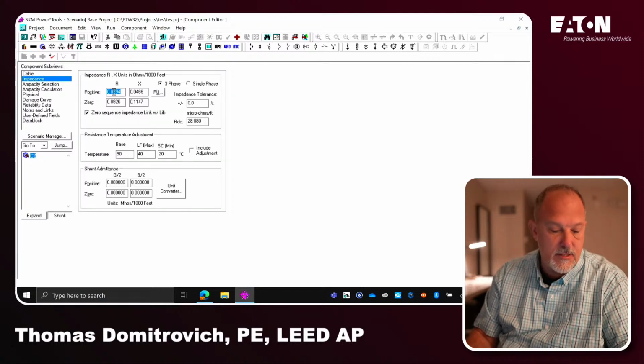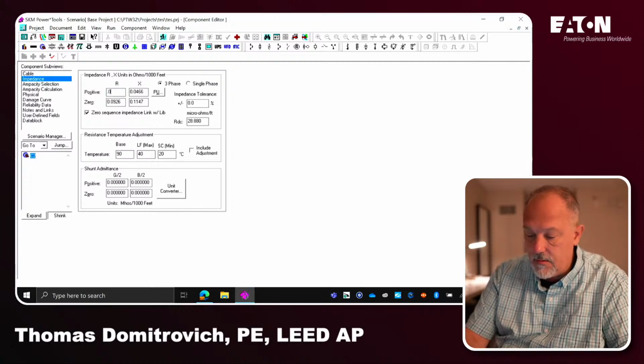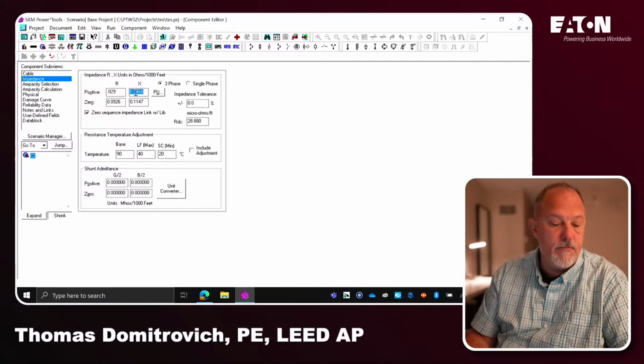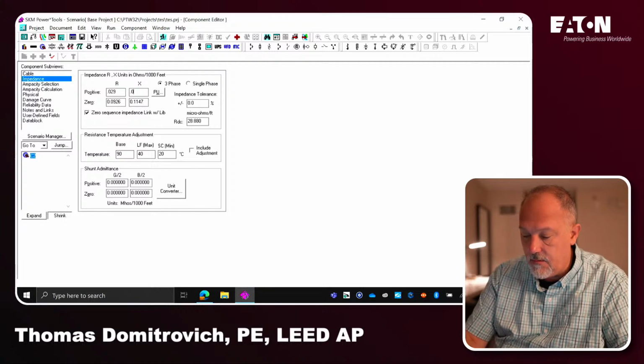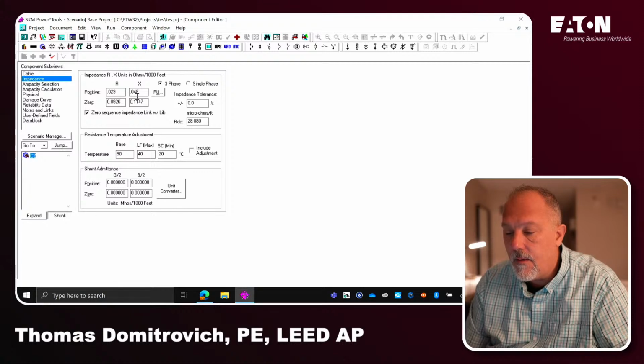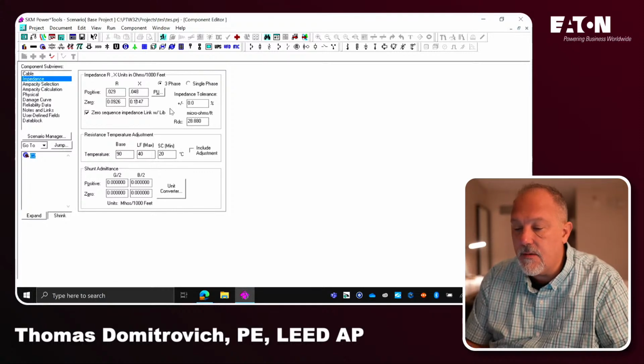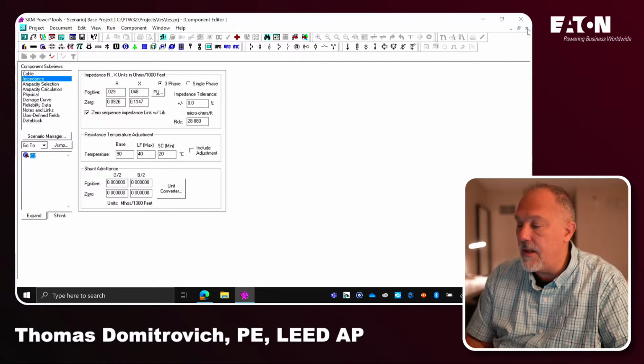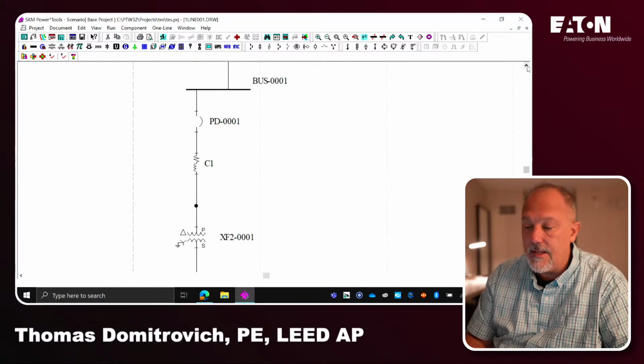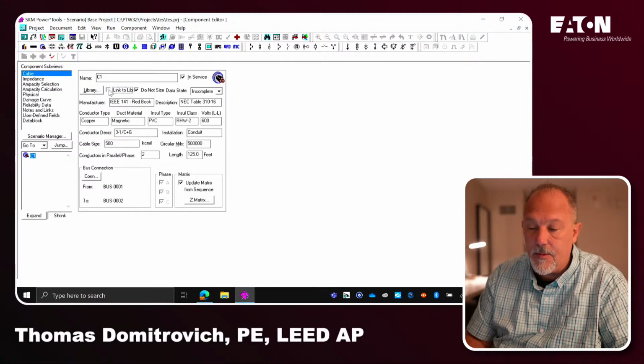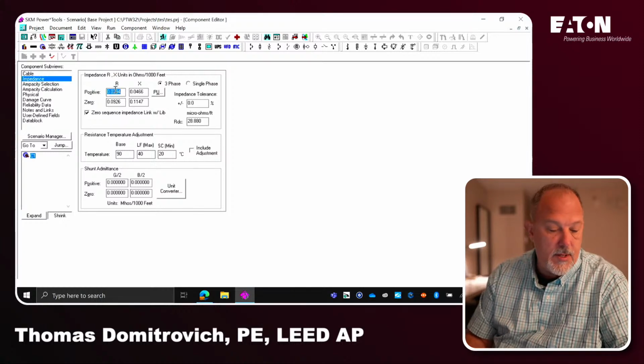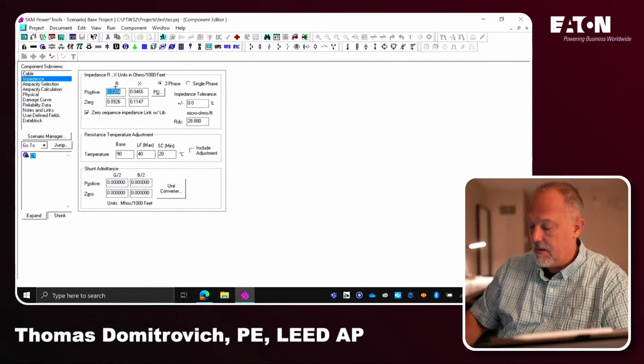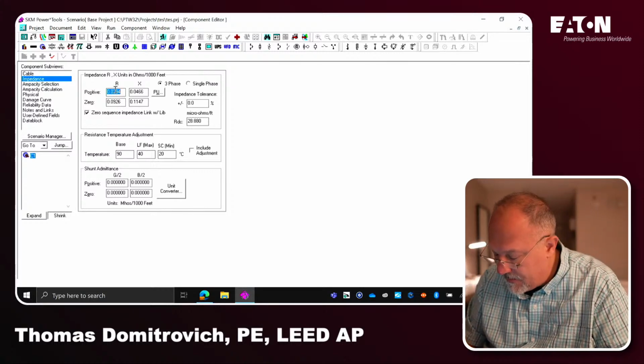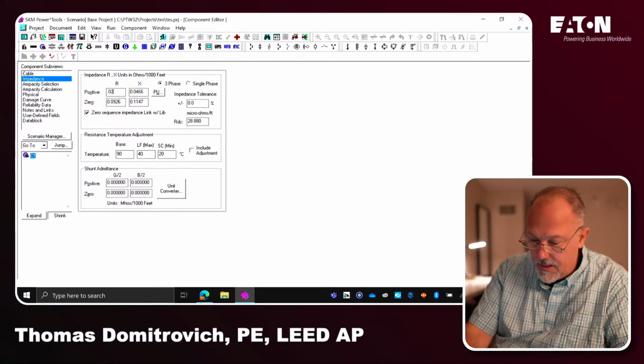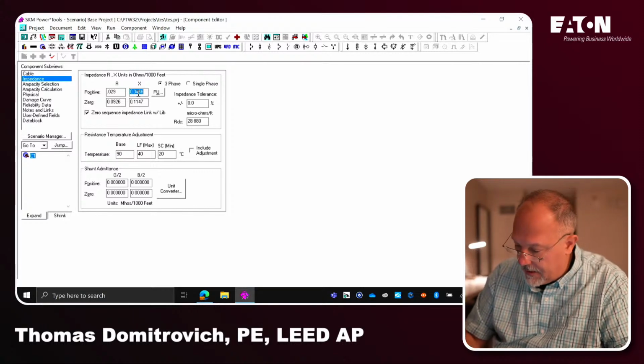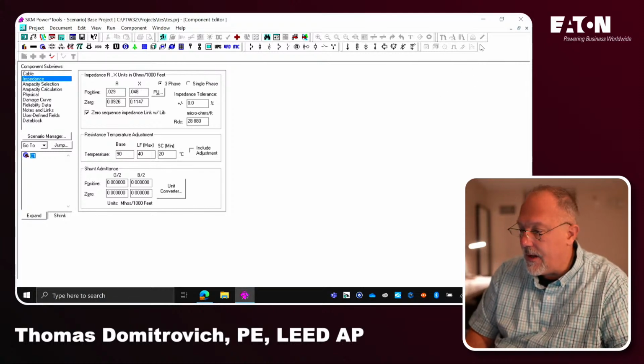There it is. Okay, so my resistance was 0.029, and my X is 0.048. I'm going to leave the zero sequence the same way, and that's it. All right. I'm going to close that. I'm going to come back up to the line side. I'm going to double click on that. I'm going to unlink from library. I'm going to come over to the impedance, and because they're both 500, I'm going to type in, I hope I'm hitting the decimal and not a comma. Yep, 0.029. And the X is 0.048. And then I close.